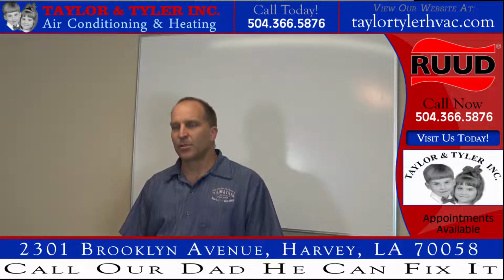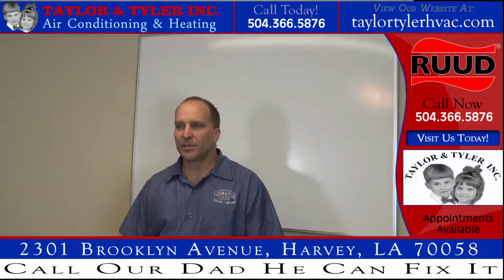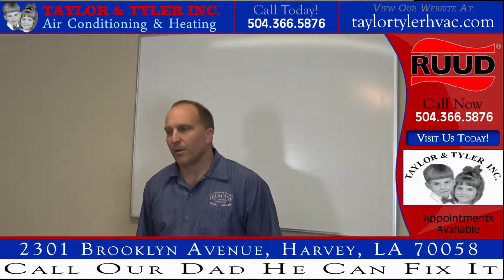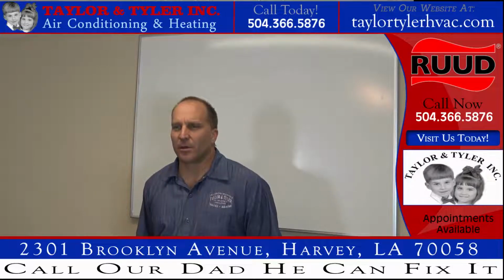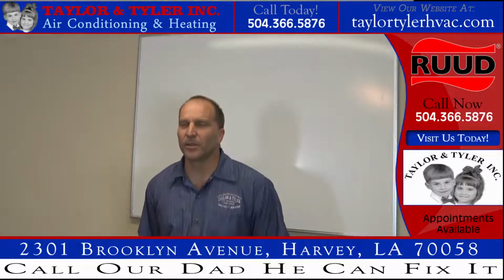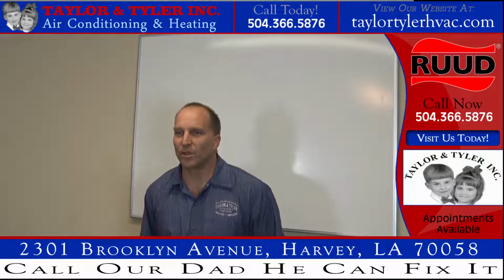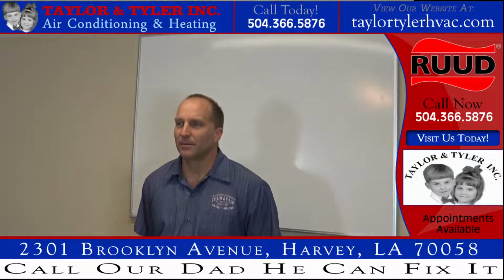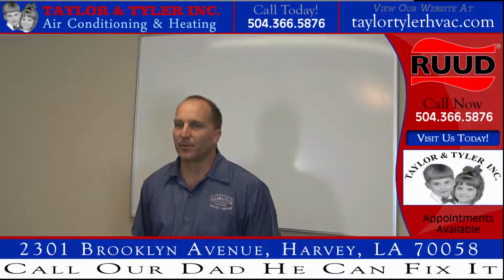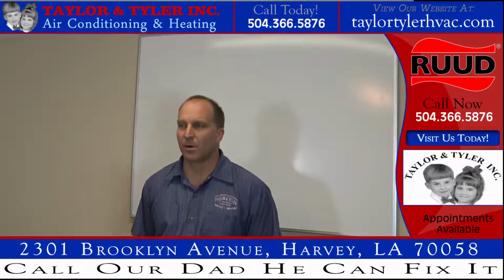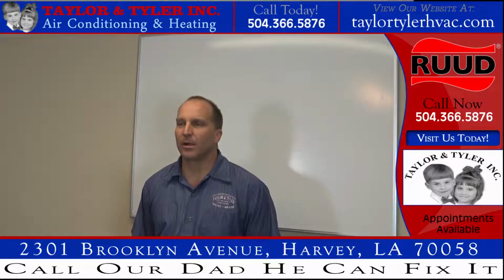Okay? So you go out there, guys, and you put your gauges on the system. And you're running a 325 pound head pressure, 118 pound suction pressure. You're running a 12 degree subcooling and a 15 degree superheat. Everything's beautiful. And it just does not cool during the middle of the day. At nighttime it cools fine. Tell me what's wrong. It's a vertical air handler in the closet.